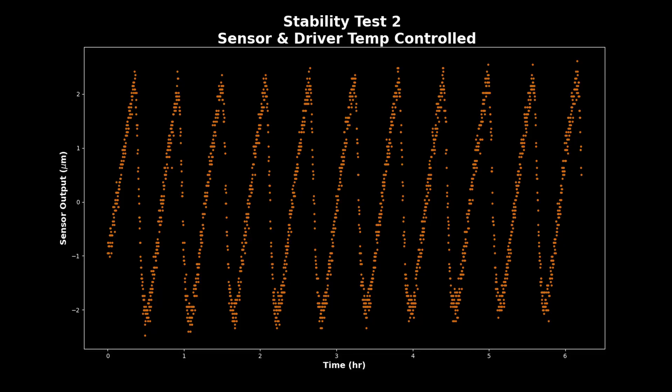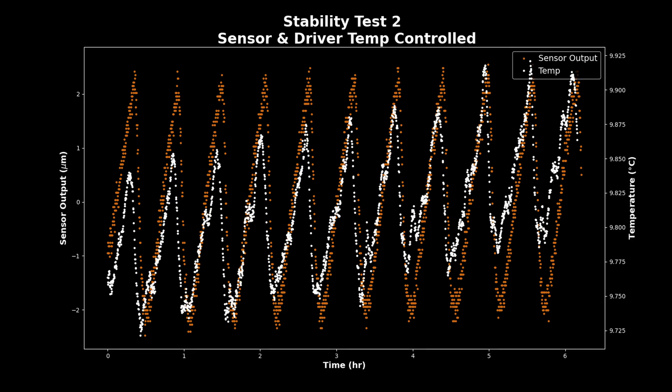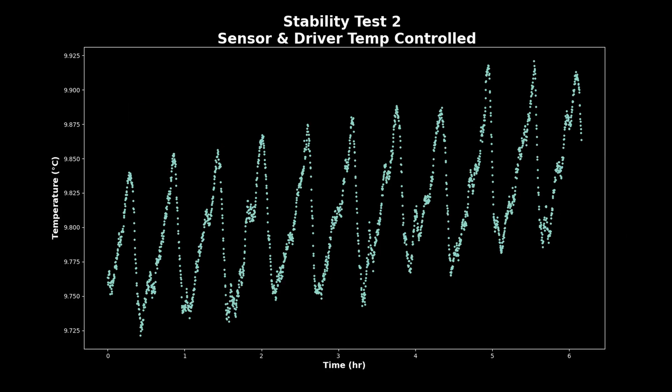This plot shows how the sensor data looked once the driver was being cooled along with the sensor body. The total variation over this five-hour period was only about plus-minus two and a half microns. And looking at the temp data over that same period, it seems pretty clear that this drift data is very much correlated with the temperature. The sawtooth pattern showing up in both of these plots is the cycling on and off of the chiller unit.